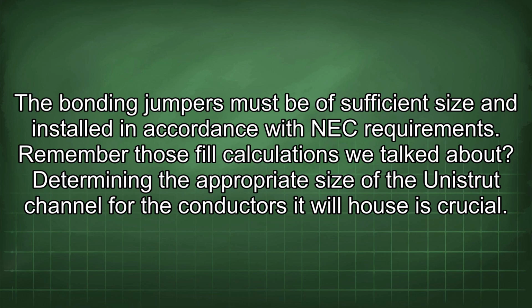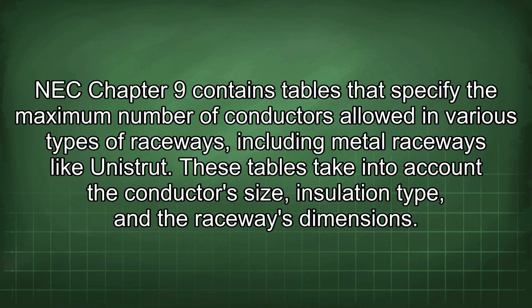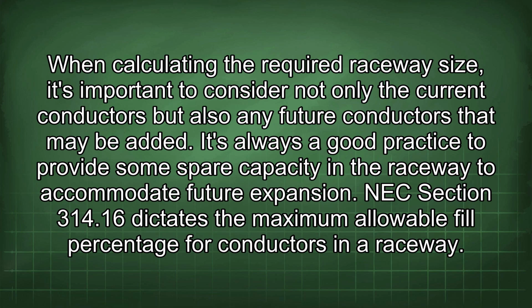Remember those fill calculations we talked about. Determining the appropriate size of the Unistrut channel for the conductors it will house is crucial. NEC Chapter 9 contains tables that specify the maximum number of conductors allowed in various types of raceways, including metal raceways like Unistrut. These tables take into account the conductor's size, insulation type, and the raceway's dimensions. When calculating the required raceway size, it's important to consider not only the current conductors but also any future conductors that may be added.